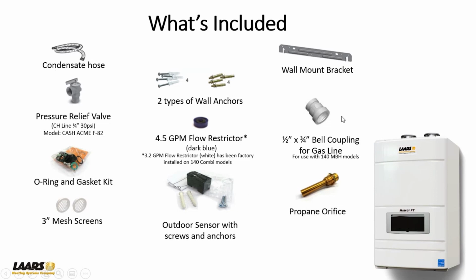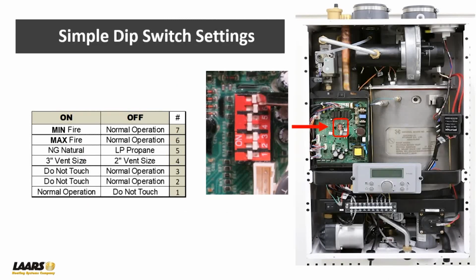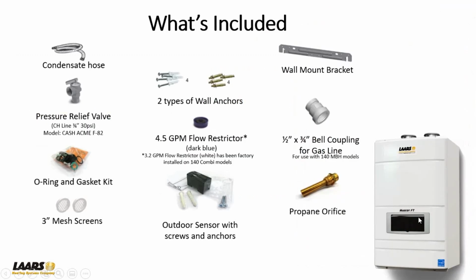The relief valves in the box on the wall hung, that gets installed right on the top of the boiler. Heating only, will show you where that location is. We also give you an O-ring gasket kit that ships with every boiler right inside the cabinet. Example of that, this little green gasket you'll see here, that is a gasket that would be used for propane conversion. And in behind the fitting here, that's where that gasket is. And so if you took the fitting off and dropped it and lost it, at least you would have another gasket there available. And that gasket kit is right here down in the lower right-hand corner.